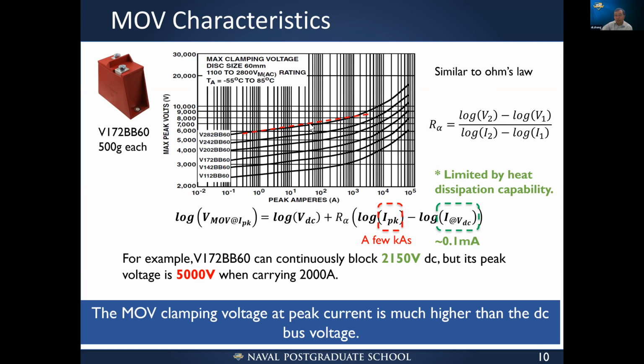So even though this is already the log scale, that's how the MOV can clamp the voltages, but the peak fault current and also the continuous leakage current differ by a few orders of magnitude. The peak current is in a few kiloamps, and the leakage current is in the range of 0.1 milliamp. That's the reason the MOV cannot really clamp the voltage as low as we want. For example, this is an MOV that can continuously block 2150 volts, which can meet the requirement, but its peak voltage will be 5,000 volts when carrying only 2,000 amps.